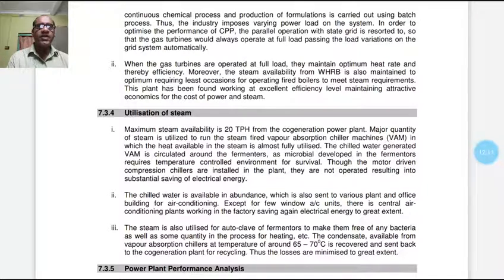In order to optimize the performance of this plant, parallel operation with the state grid is resorted to, so that the gas turbine would always operate at full load, passing the load variation on to the grid system automatically. When the gas turbines are operated at full load, they maintain optimum heat rate and thereby efficiency. Moreover, the steam availability from the waste heat recovery boiler is also maintained to optimum requirement, with least occasions for operating the fired boiler to meet steam requirement. This plant has been found working at excellent efficiency level, maintaining attractive economics for the cost of power and steam.